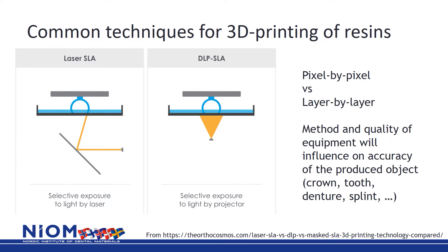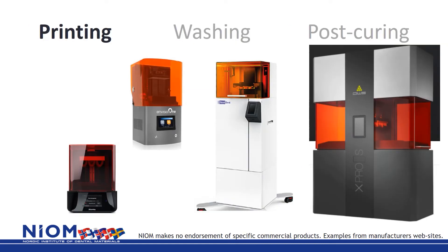There are also other methods and materials available, such as jetting techniques, which may become important for the dental industry in the future. A lot of different printers are available in various sizes. They may have different dominant wavelengths — 385 or 405 nanometers — and have different working areas, being able to produce one or more objects at the same time. The speed, accuracy, and pixel size will vary between printers.